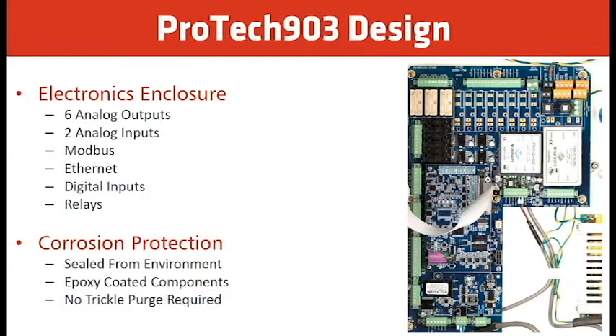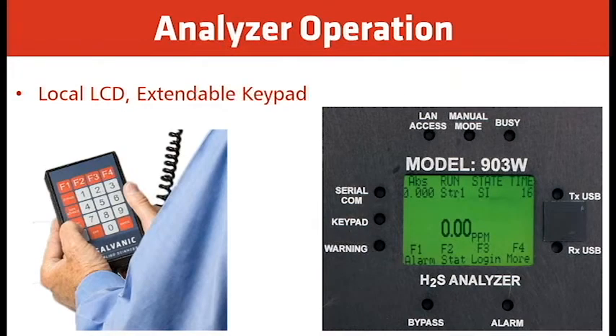Corrosion protection includes being sealed from the environment and epoxy-coated components, and no purge or trickle purge is required. The analyzer comes with a local LCD and an intrinsically safe extendable keypad — so you do not have to declassify the area to make changes, especially for Class 1 Div 1. The keypad allows you to modify software settings, initiate AutoCal, and reset the tape counter when you replace the tape, for example resetting it back to 330 for a 330-foot tape.